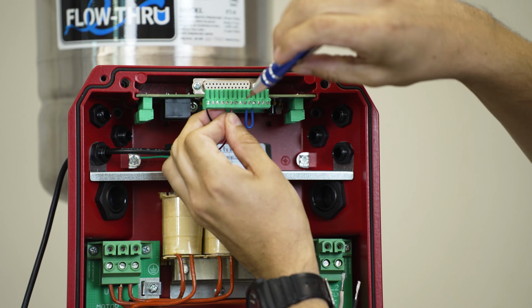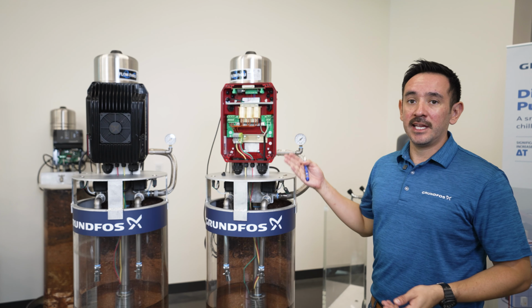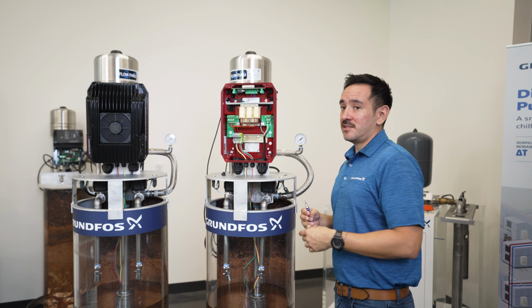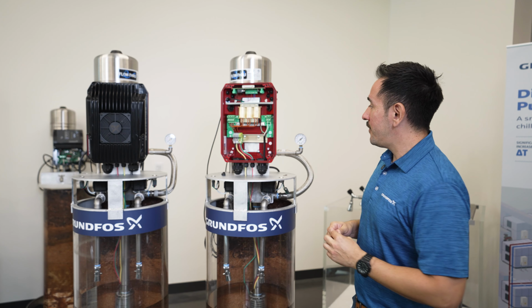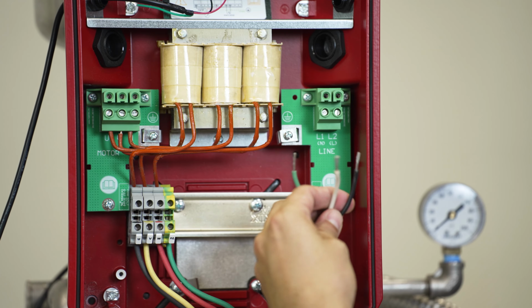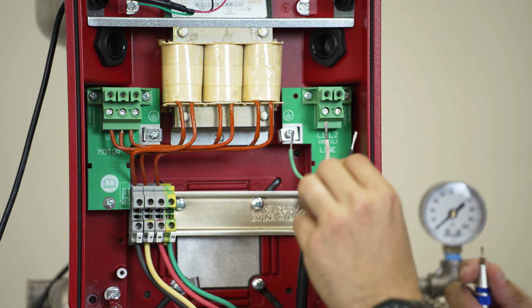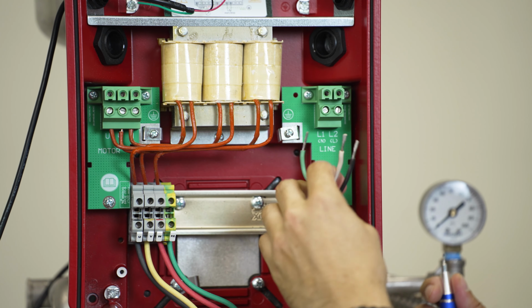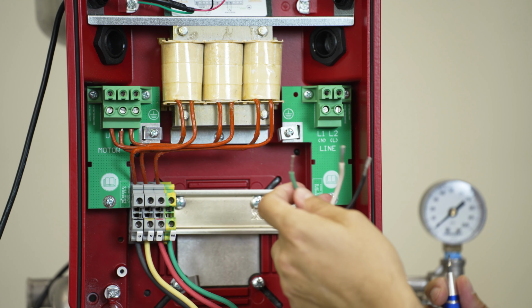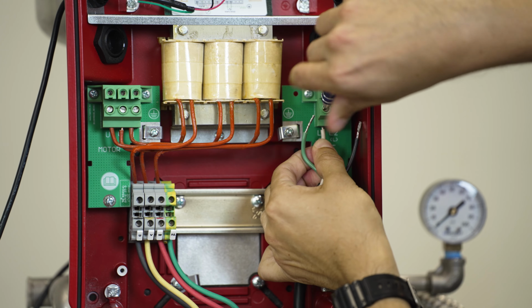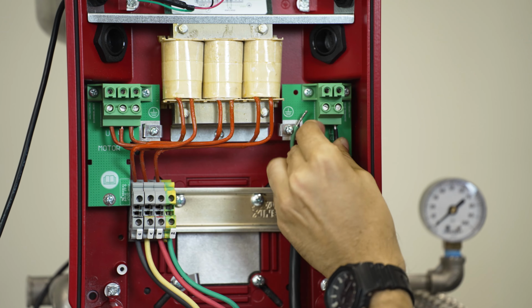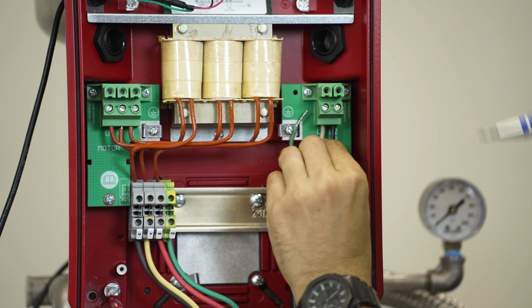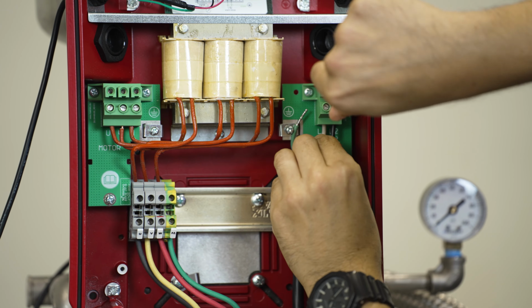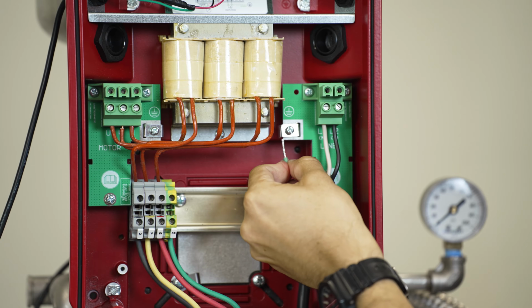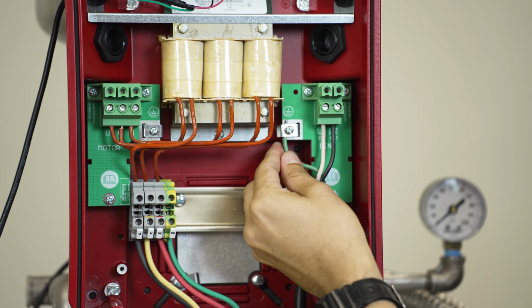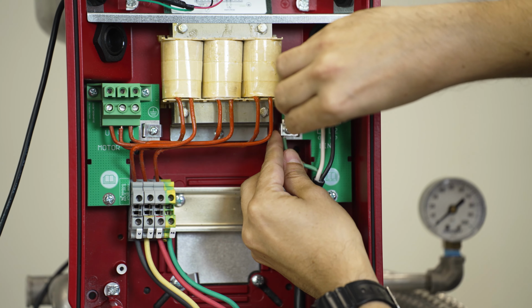Now that we have the sensor connected, we'll move on to the incoming power wires. Because this is a single-phase incoming supply, we will have 3 wires. We will have your neutral, you will have your line power wire, and then we will have your ground wire. White cable will go into terminal L1. Then you have your black wire, which is your line, will go into L2, also labeled L.